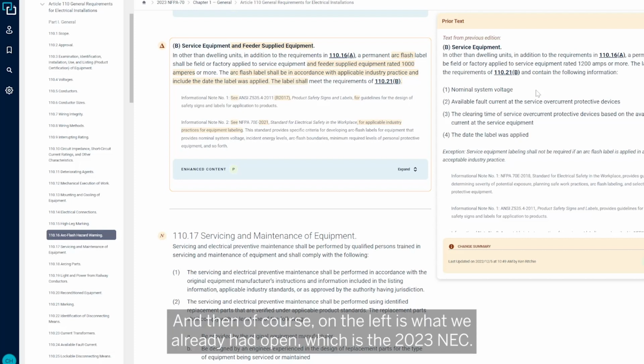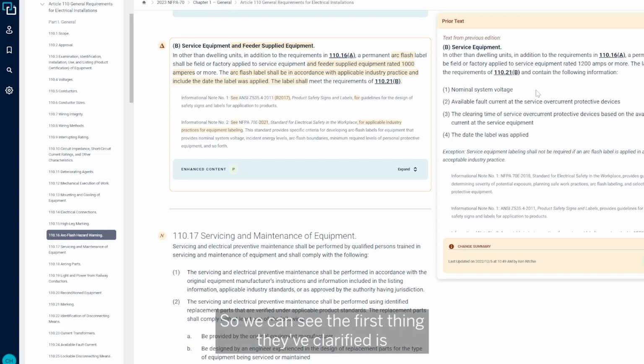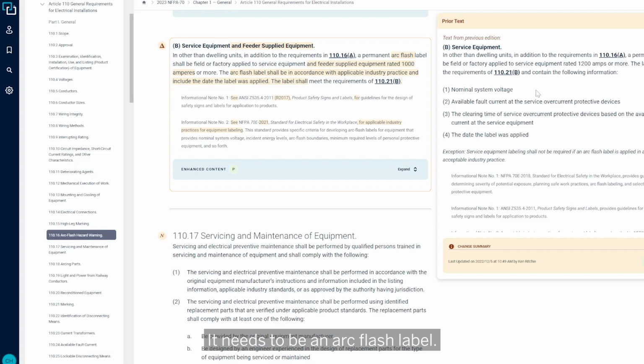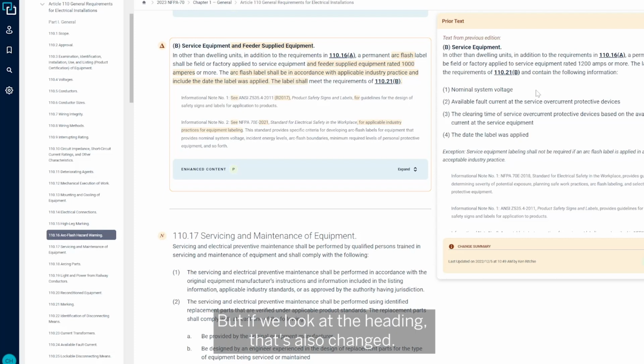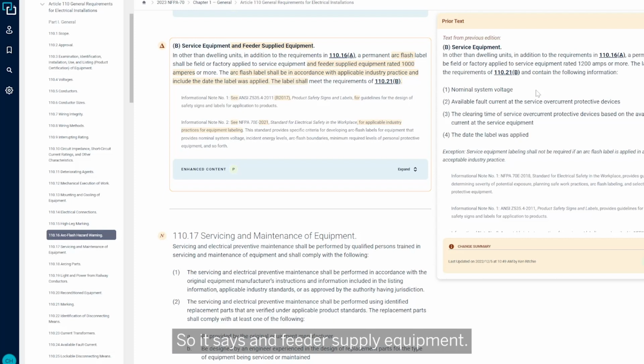And then, of course, on the left is what we already had open, which is the 2023 NEC. So we can see the first thing they've clarified is that it's not just any permanent label. It needs to be an arc flash label. That's the intent of this section. But if we look at the heading, that's also changed. So it says, and feeder supply equipment.